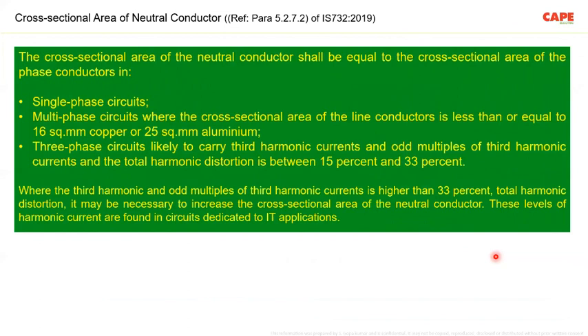The cross-sectional area of the neutral conductor is also equally important, but often people think that neutral is not important. So if the phase is 6 square mm, let us use 2.5 square mm for the neutral conductor and 2.5 square mm for the earth conductor, which is actually wrong.